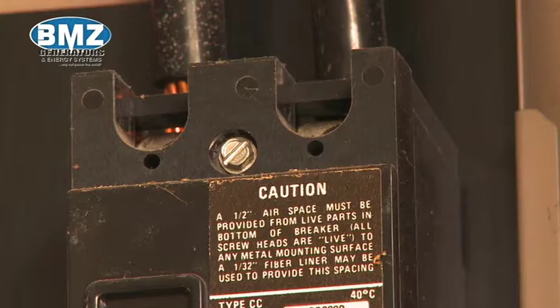When power comes in, single phase has 2 lines of power, 3 phase has 3 lines of power, and that power comes in different loads. If that load isn't relatively equitable, you're only going to get use of the lowest load, but you're going to pay a rate based on the highest load.